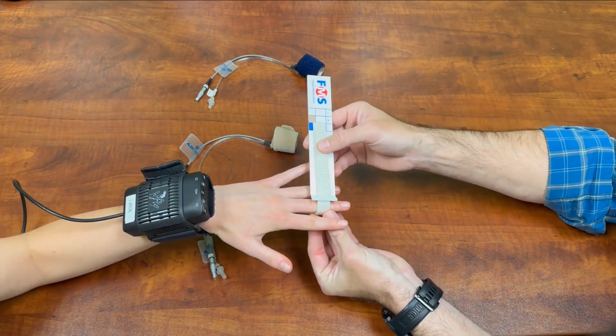There are 3 different cuff sizes based on the circumference of the subject's finger: small, medium, and large. Each NOVA is supplied with a fitting guide to help ensure proper cuff size fitting. Position the cuff on the middle phalanx of either the middle, ring, or index finger. Apply the cuff with the cables on the palmar side of the finger. The sensor pressure points should be centered between the knuckles and placed symmetrically. The cuff should be wrapped tightly around the finger. Please be sure to not completely unravel the finger cuff or you can damage the bladder.